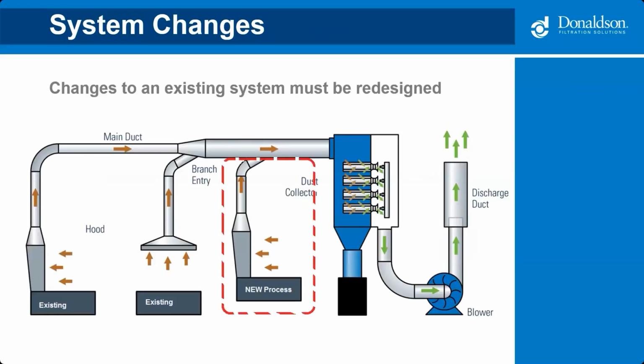One thing I want to highlight, it's really not a maintenance item, but we see it a lot as we help our customers with services. So I just wanted to call it out for the group. It's really important that you look at this as an entire designed system. So the dust collector is part of that entire system. The fan is important, the ductwork, the hoods, the sizing of the ductwork, all of these things are designed together as a system. And so it's very important that you think of it that way.